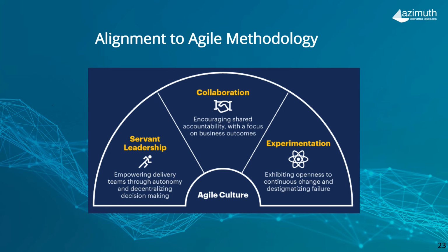Let me give you an example. I worked with this large medical device company. They had a failure in their testing. Very early on, quality said it was due to them not understanding the validation. They didn't test everything. My argument was they didn't understand what they needed in the first place, what their intended use was, how that should work, what was acceptable to them. Thus, their root cause was a validation failure, and mine was that it wasn't a validation failure. It was further back. It was a business decision or intended usage failure.